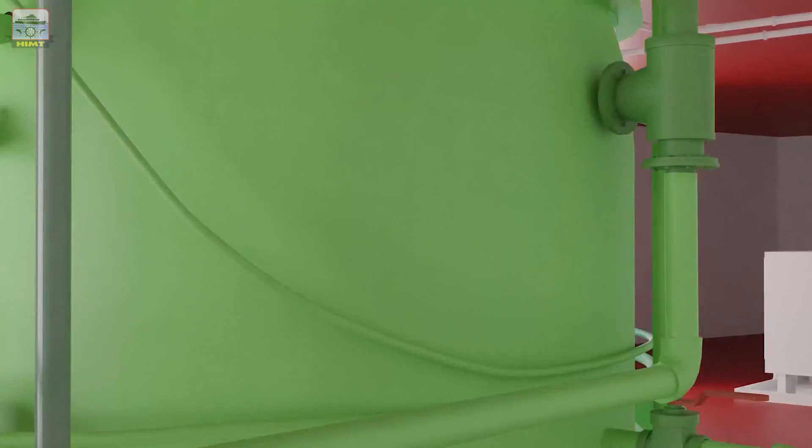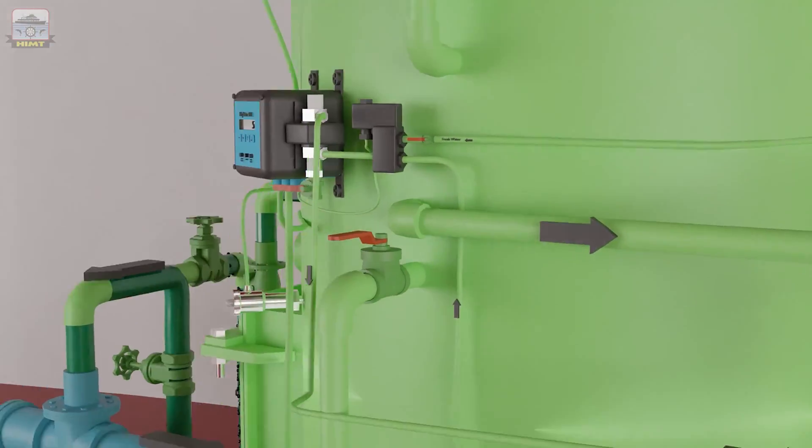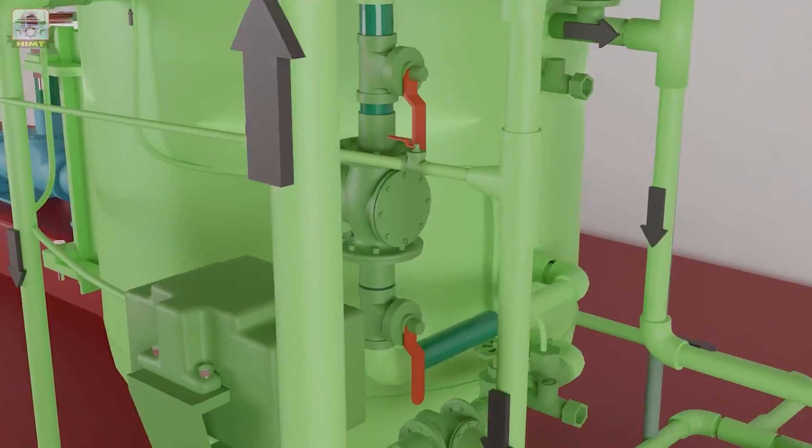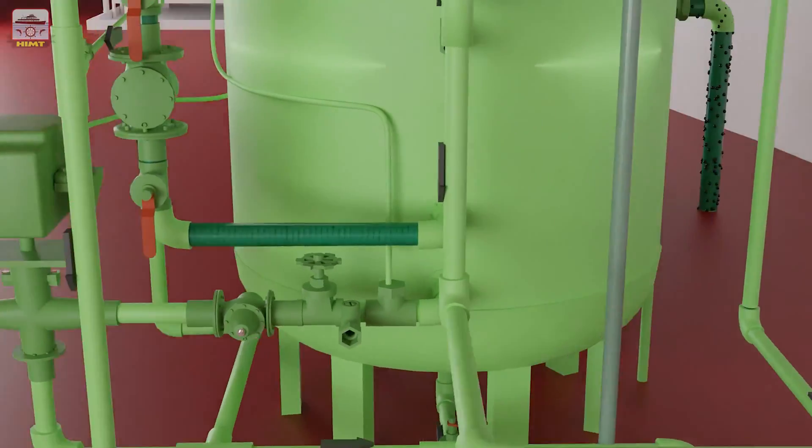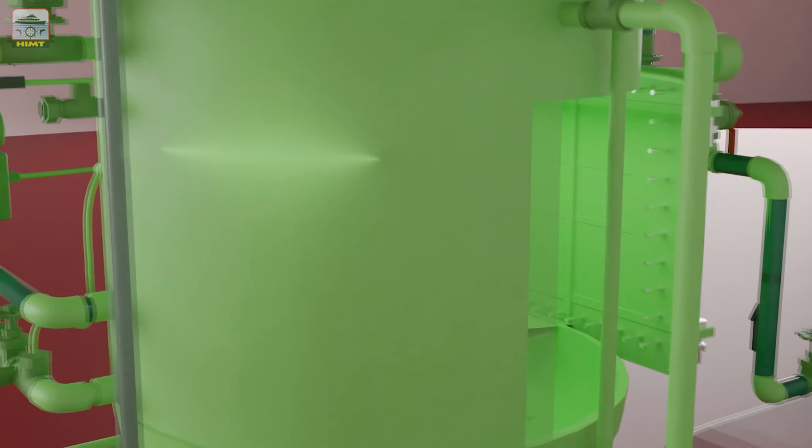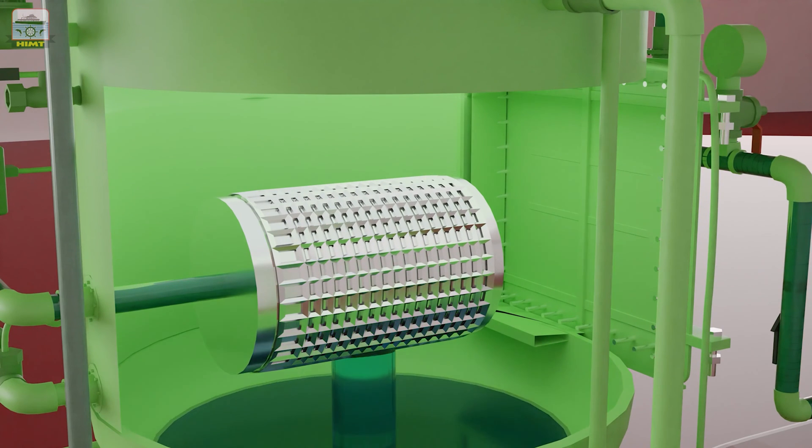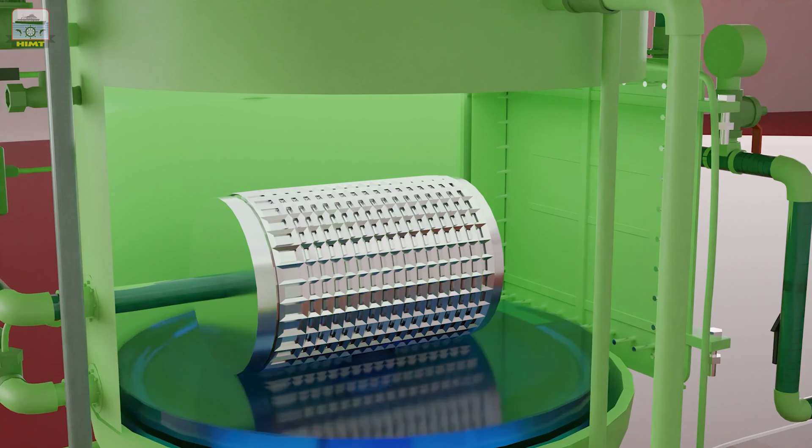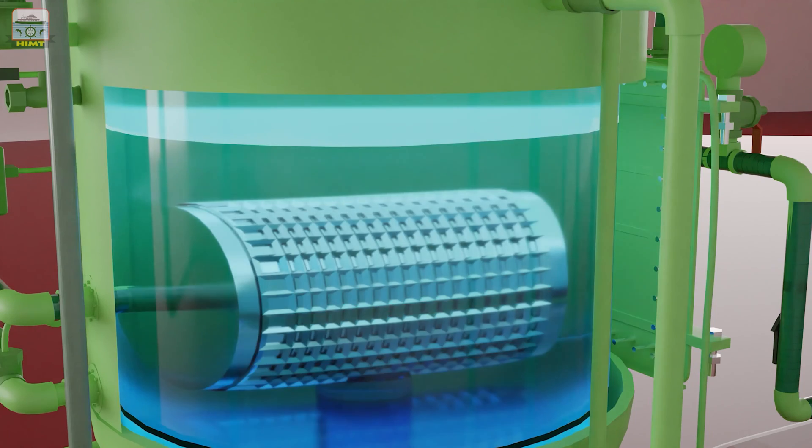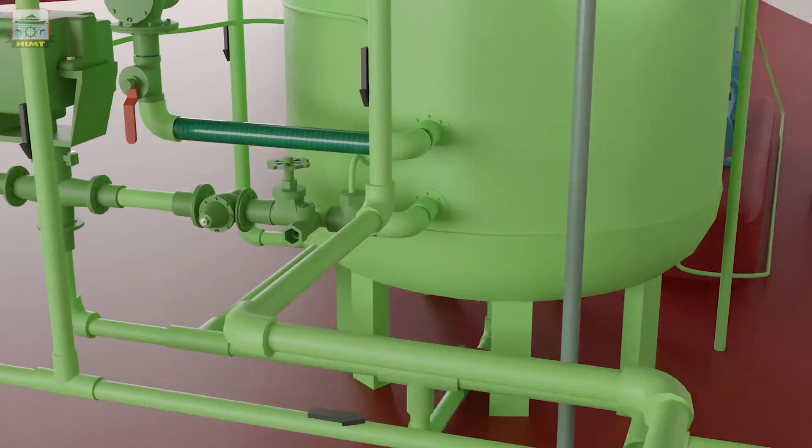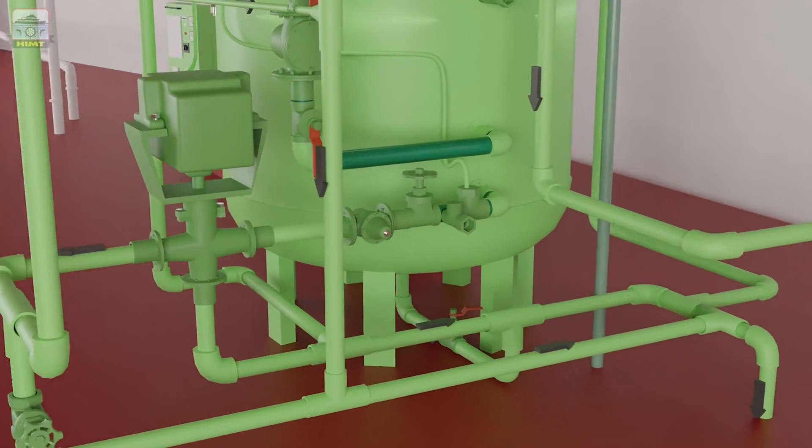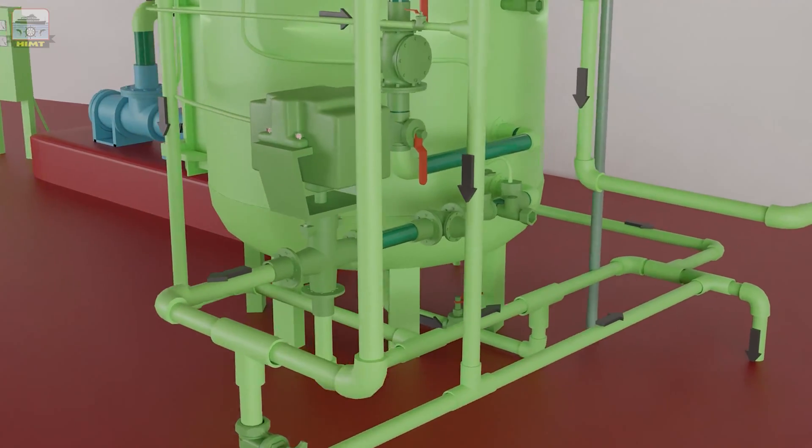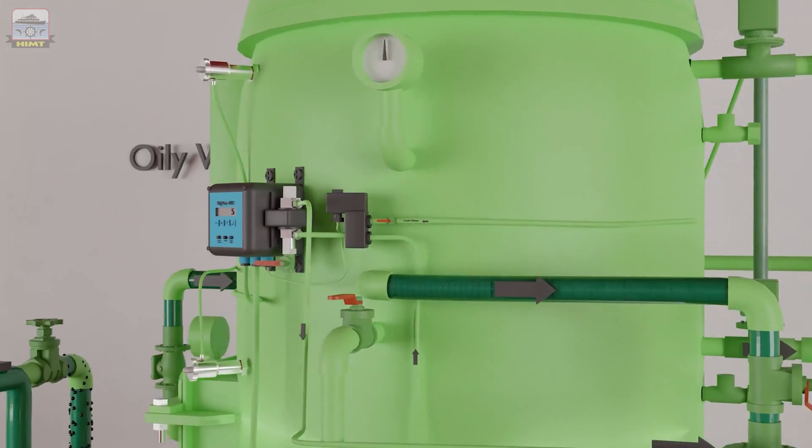After filling up the primary chamber, the water flows into the secondary chamber. We can see the water coming out of the coalescence filter and filling up the secondary chamber. After filling up the secondary chamber, water exits through the three-way valve to the overboard line when the oil content is less than 15 ppm.